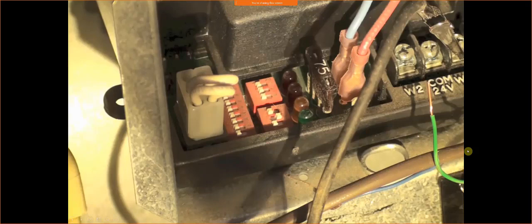8 or 9 times out of 10, it's never the pressure switch that's at fault. It's always a blockage or an obstruction, either in the flue or our heat exchanger. For example, a high efficiency system has 2 heat exchangers. That second heat exchanger is plugged up or filled up with water. So we have to ensure that we know what's going on and really dial in and figure out that this is the problem. We don't want to be that parts changing warrior. Hey, let's throw in a new pressure switch. It may work, it may not. You also want to throw in one that's identical or very similar to the settings that it's requiring. So, just a little tidbit for you guys.